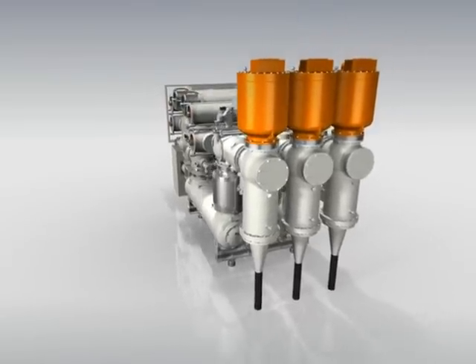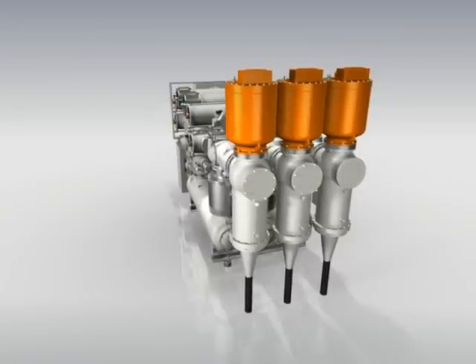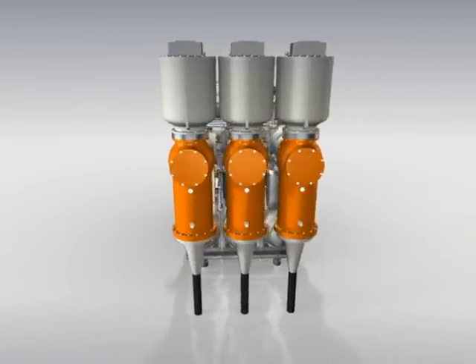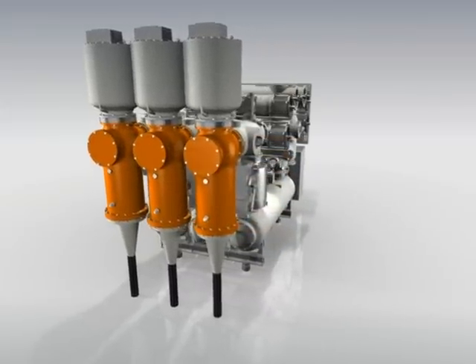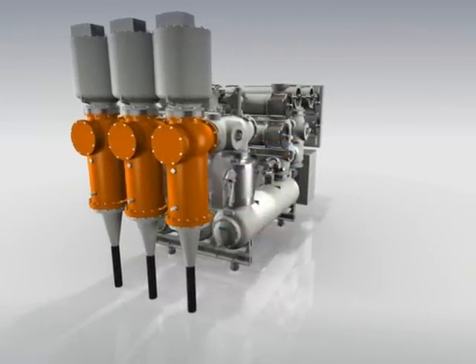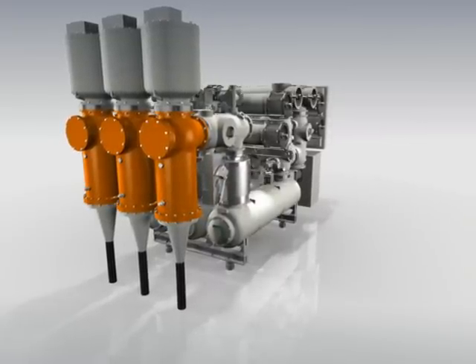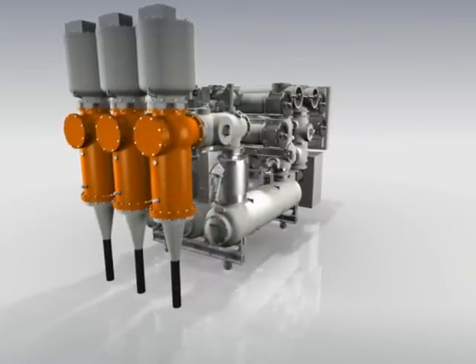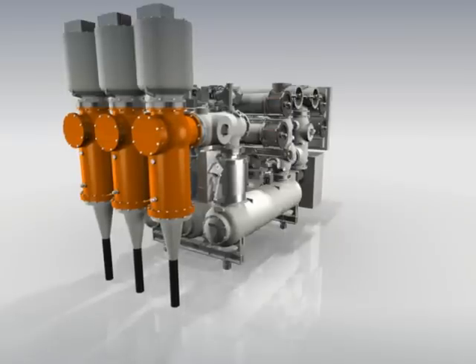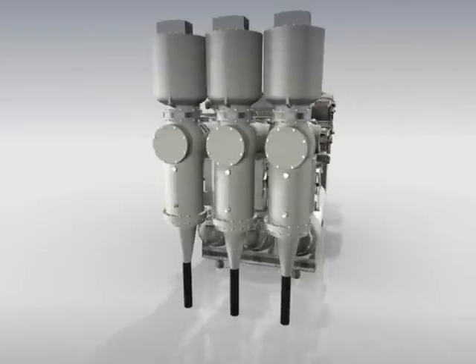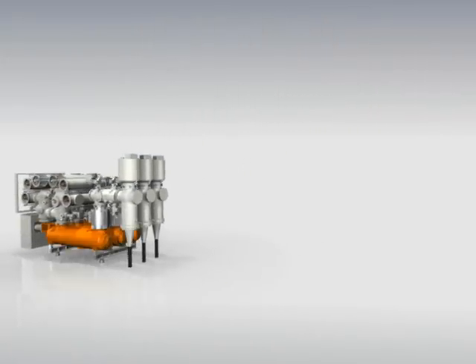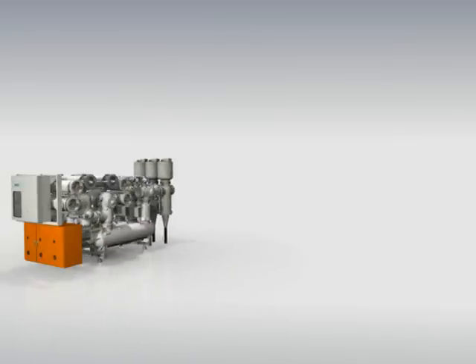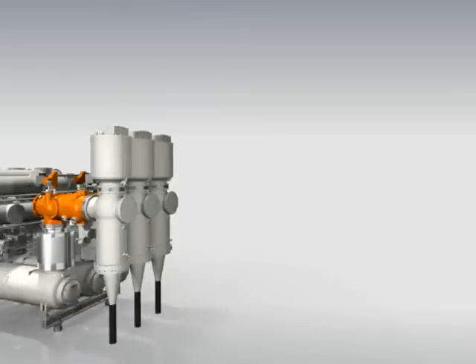Voltage transformers, usually of inductive type, are also used for measuring and protection tasks. The cable termination module links the gas-insulated switchgear with a high-voltage cable. This module is the transition point from the sulfur hexafluoride gas insulation to other insulation media. It can be fitted with a conventionally fixed cable connection or with a modern dry plug-in cable connection. To provide for maximum versatility, a number of additional connecting and termination modules are available.